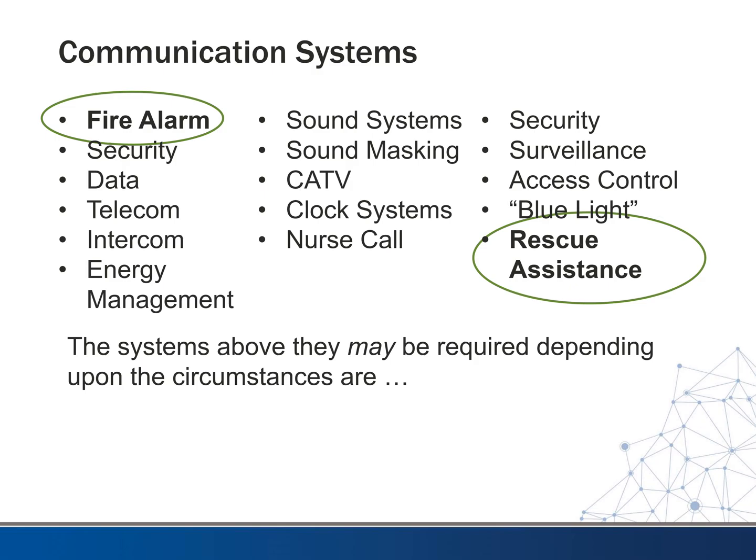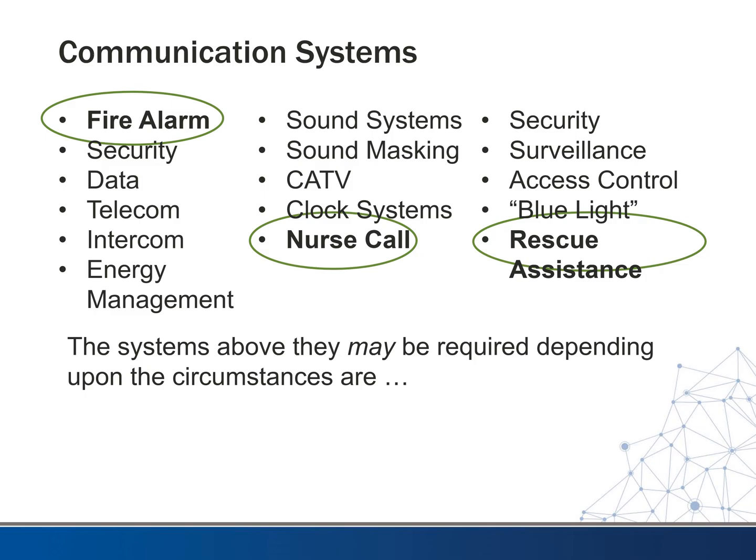The other required system is rescue assistance. If you have a multi-story building that utilizes an elevator — usually for buildings four stories or taller — we dedicate areas in the stairwell where someone in a wheelchair can get help. You're not supposed to use elevators during a fire, so if they can't go down the stairs by themselves, we designate areas of rescue assistance with signage. In that stairwell we put some means of communication, usually down to a central location at the front desk or front door.